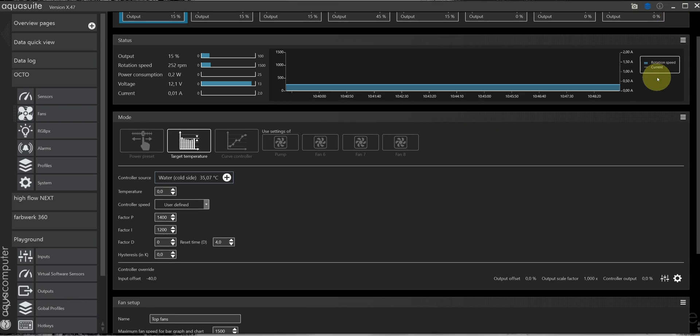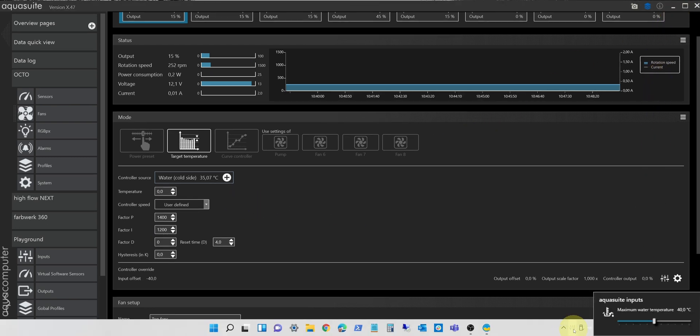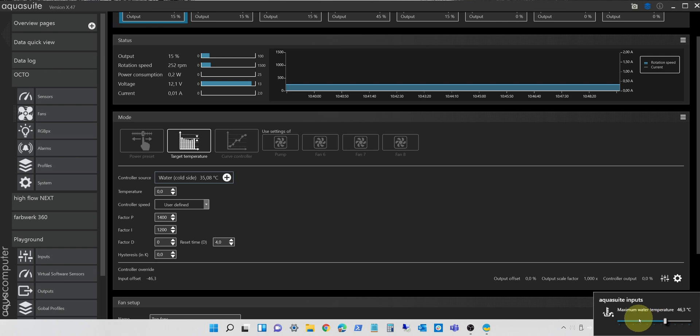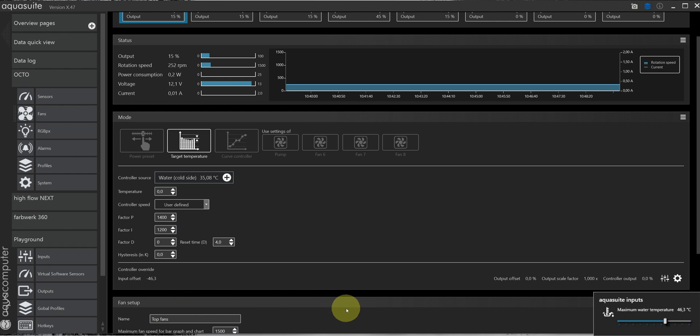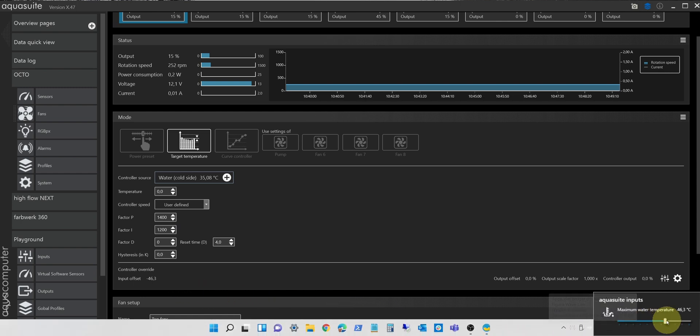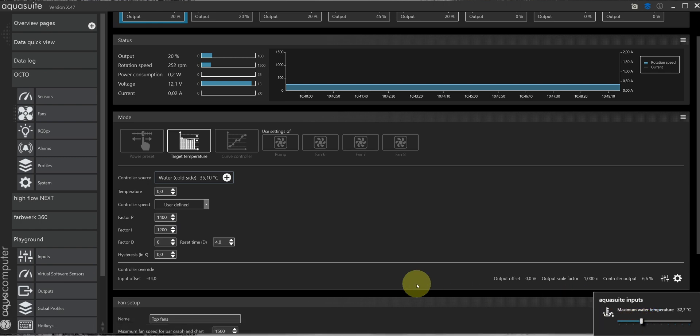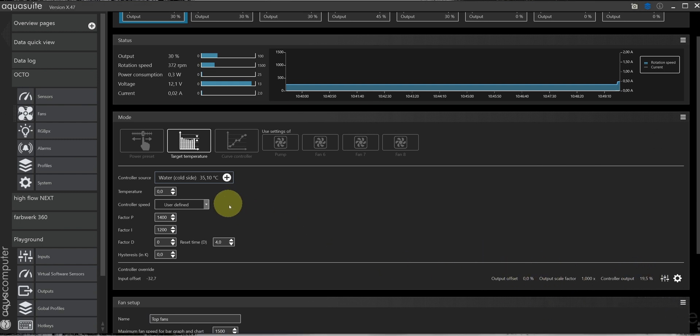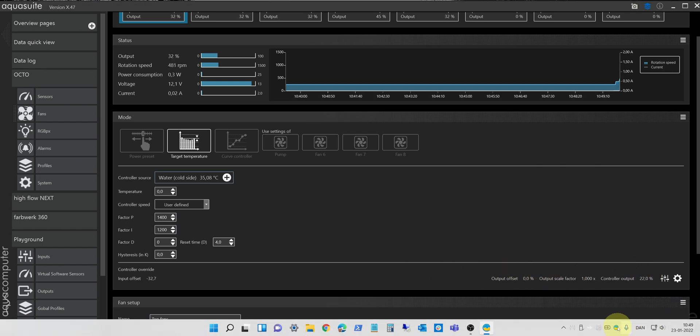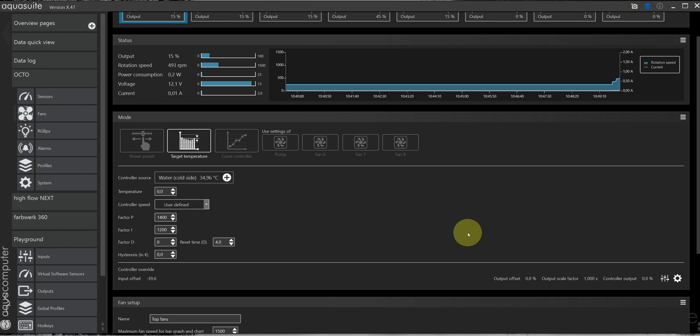If I change the input value, you can see the input offset reflects the change. And if I drag it below the current water temperature, you'll see the controller begins to raise the controller output to speed up the fans, to cool the water down to whatever I've set. I'll put it back to 40. And the control output is back to zero.